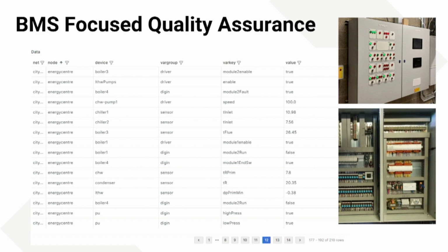Low temperature hot water system, sensor, differential pressure - these are all data points in the BMS. Every boiler point, every VART temperature, every sensor is in the BMS. If you label it correctly, which is about a day's work, you have this at your disposal.